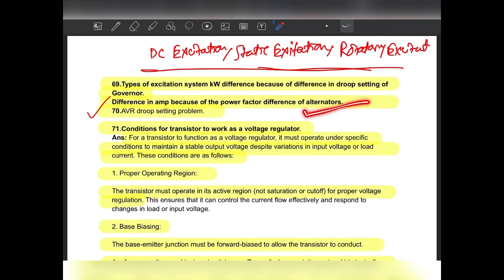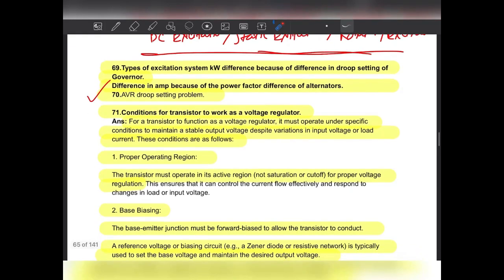Difference in ampere because of the power factor difference of the alternator. Okay, if there is a difference in ampere of a generator, what do we have to do? Because of the ampere difference, the power factor will be different, because there will be a phase difference between the current and voltage. So we have to adjust the AVR droop setting, because the AVR basically adjusts the field excitation current, and due to this our voltage will be maintained. So we have to maintain the AVR droop setting. Okay, next: condition for a transistor to work as a voltage regulator and proper biasing.